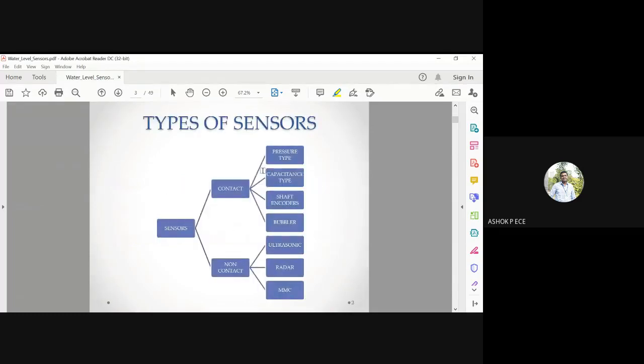For water level sensors, there are contact and non-contact types. Contact types include pressure type, capacitor type, shaft encoder type, and bubbler type. Non-contact types include ultrasonic, radar, and MMC type. Contact means the sensor comes in physical contact with water, while non-contact means the measurement is done from a distance.